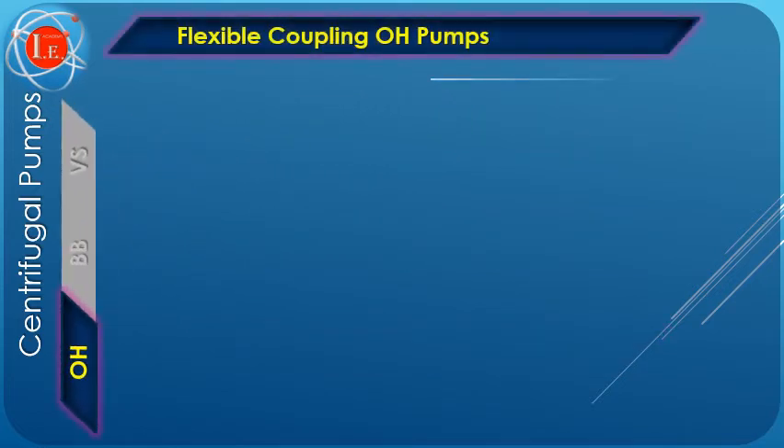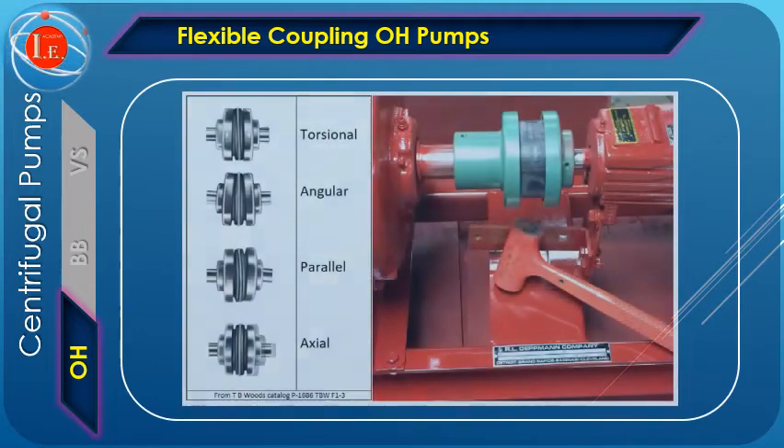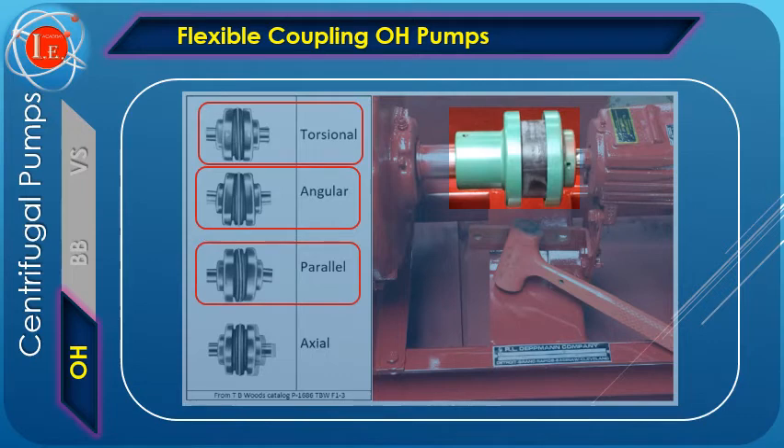OH pumps, flexibly coupled, feature a separate bearing assembly in addition to the motor. Flexible couplings are usually used to transmit torque from one shaft to another when the two shafts can be slightly misaligned. They can accommodate angular misalignment up to 3 degrees and parallel misalignment to a certain degree. In addition, they can also be used for vibration damping or noise reduction.